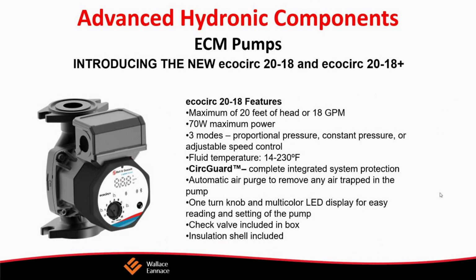If we use ECM pumps, this hydronic heating system has, on this 10,000 square foot house, 40 circulators, each consuming 90 watts. The design load is 400,000 BTU per hour. So the distribution efficiency is 400,000 divided by 40 times 90 watts, or 111 BTUs per hour per watt. Realistically, that's not that much better. 111 BTUs per hour per watt is not much better than 94. In some ways it's almost the same as the forced air system.